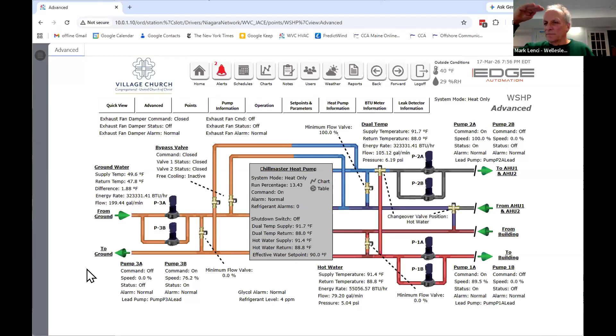Right now we're running at 13% capacity to heat it at today's temperature. Here's the water coming from the ground at about 48 to 49 degrees, and it goes into the heat pumps. It gets heated up and comes out at 91 degrees, going out to our radiators. We have one of those pumps running, at full flow at about 92 degrees, out to the air handling units, which then heat the rooms. You can go back and graph anything you want.